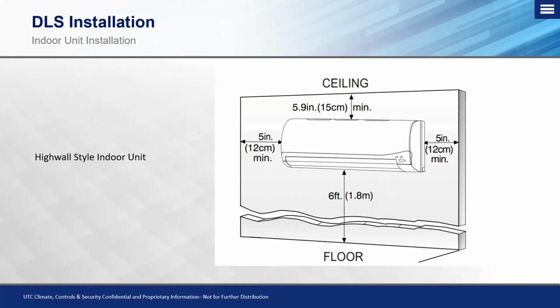So for indoor unit clearances, we're going to start with the high wall indoor unit. From the top side of the unit, for minimum space to allow for proper return airflow, we need at least 6 inches from the top of the unit to the ceiling itself. If you look on the diagram, from the left side and right side we need a minimum of 5 inches for service clearance, and the unit should be mounted at least 6 feet from the floor.